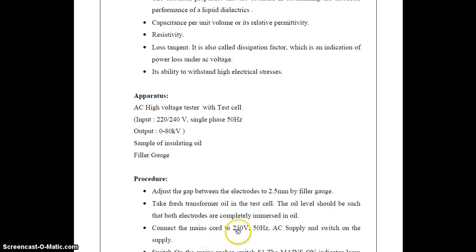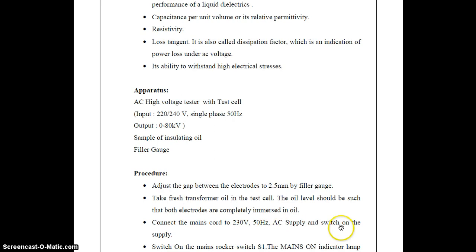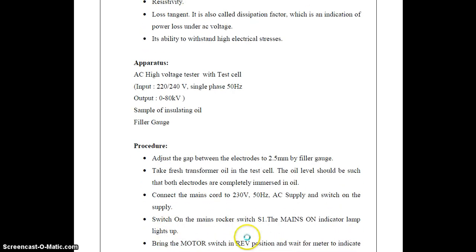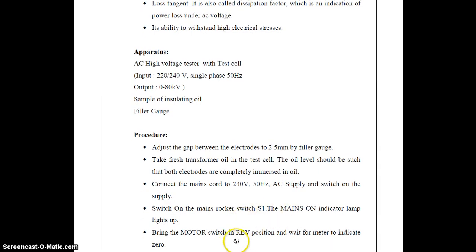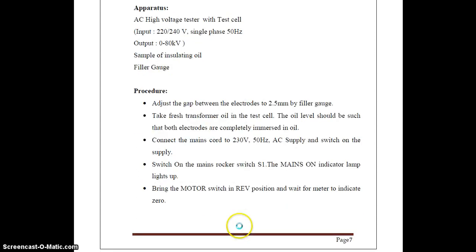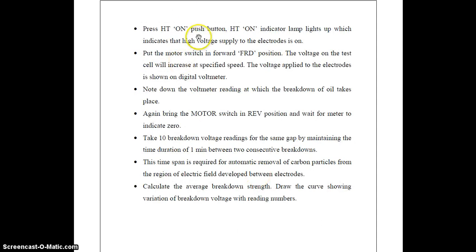Connect the main cord to the 230 volt 50 Hz AC supply and switch on the supply. Then switch on the main rocker switch S1. The mains on indicator lamp lights up. Bring the motor switch to the reverse position and wait for the meter to indicate 0. Then press the HT 'ON' push button. The HT 'ON' indicator lamp lights up, which indicates high voltage supply is flowing through the electrode. Then put the motor switch in the forward position.